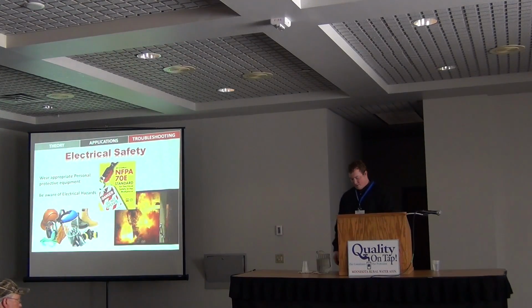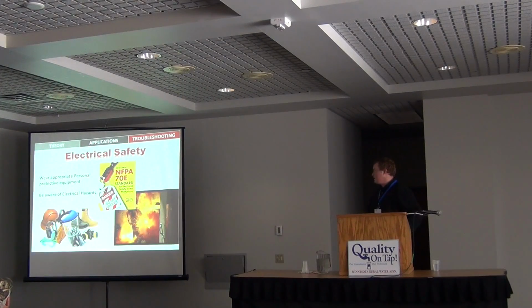I want to talk a little bit more here about electrical safety. NFPA 70E is the electrical standards in the workplace. It's a very, very good book, and if you're an operator, if you're a superintendent, or if you're even doing stuff on equipment that might be energized, you should pick up a copy of this, because it talks about lockout tagout standards, it talks about PPE, it talks about different procedures on how to approach equipment that may or may not be energized.